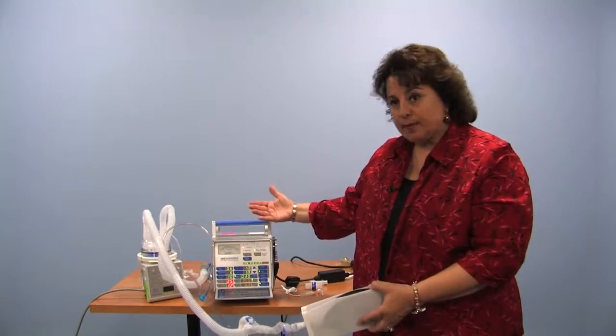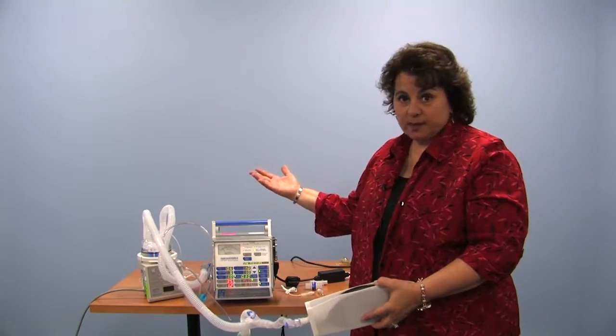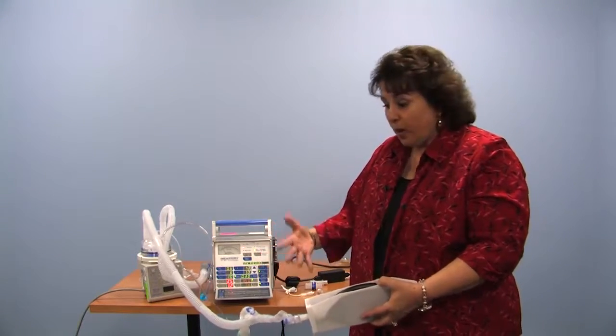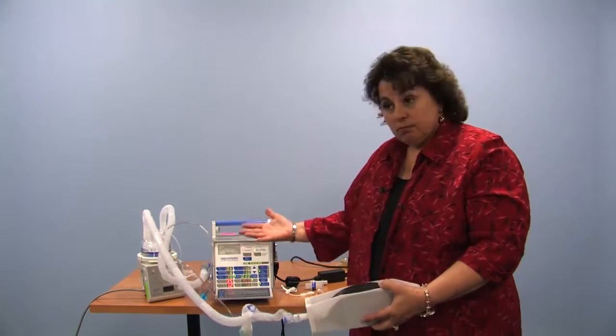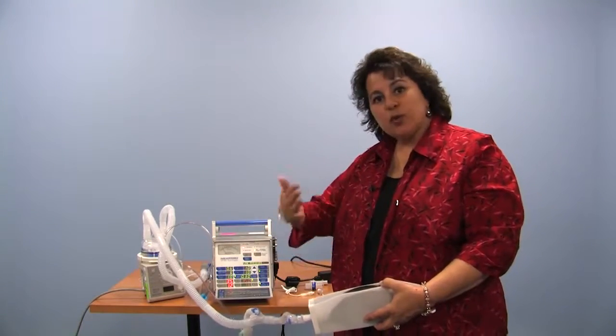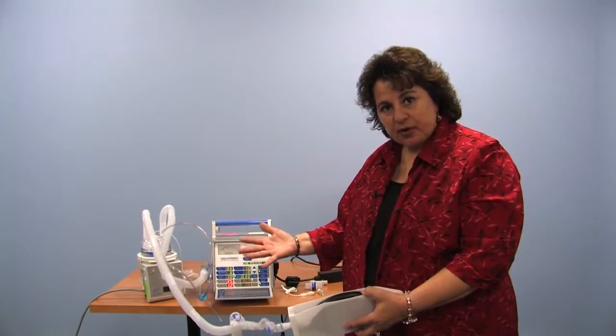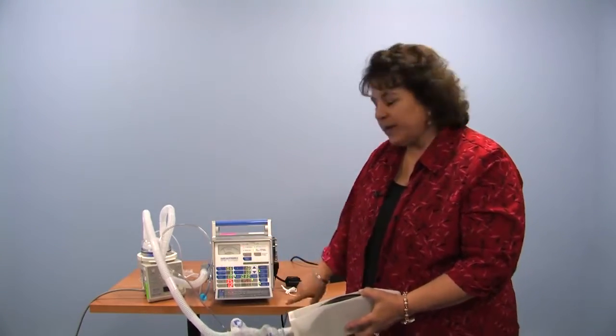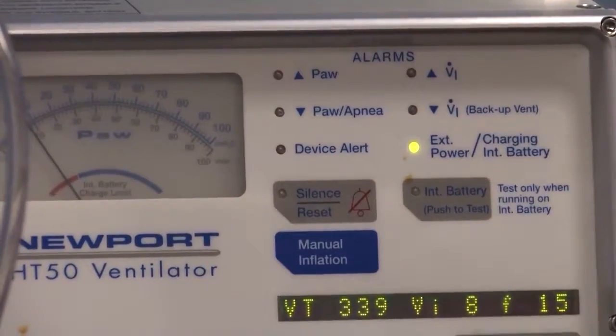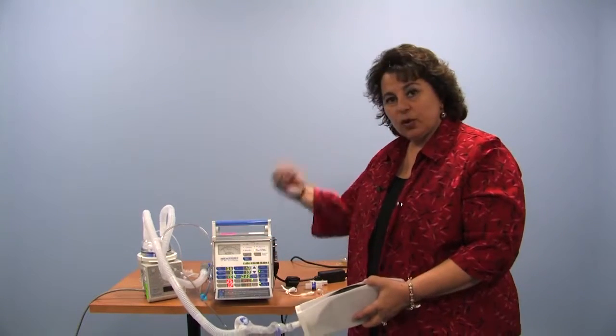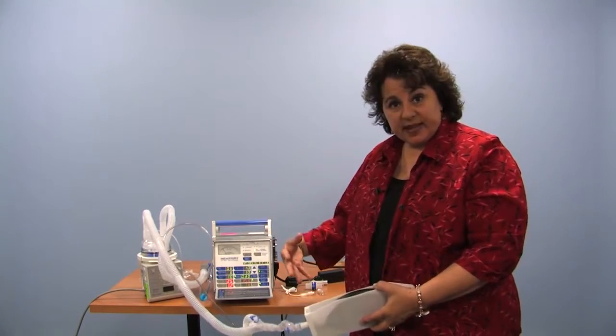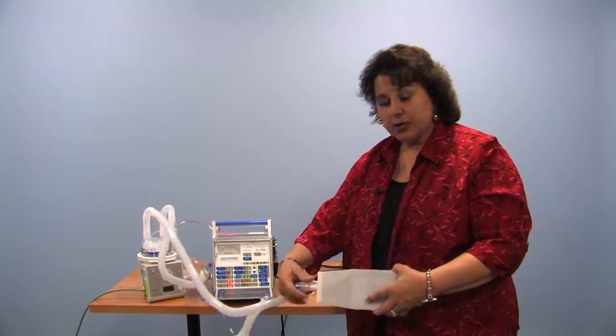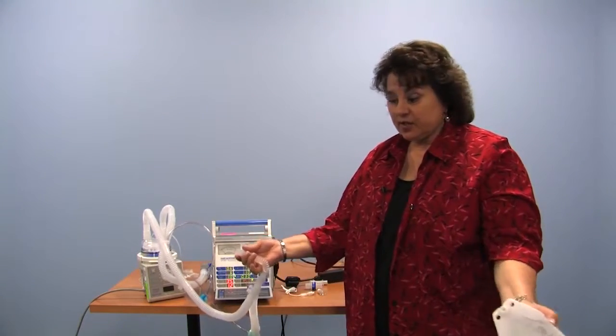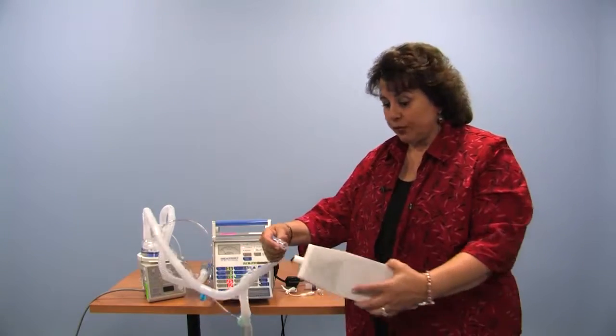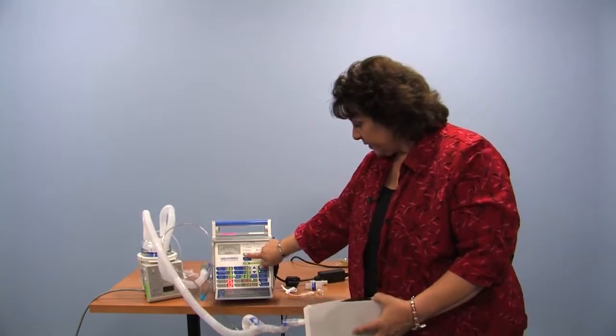Okay, you walk back into the room. You heard an alarm. You no longer hear an alarm. But you see low pressure went off. What are you going to do? Well, the child's fine, so something must have happened. Maybe they yawned and the pressure wasn't met, but everything appears to be doing very well. You come over and you reset the button. So now the lights are not on anymore. When an alarm happens, you'll hear it, you'll see it. It will reset itself if the condition is reset. Certainly if the child falls off, disconnected from the ventilator, and it's not put back on, you're coming into the room. You have to reconnect your child to the ventilator and reset the alarm.